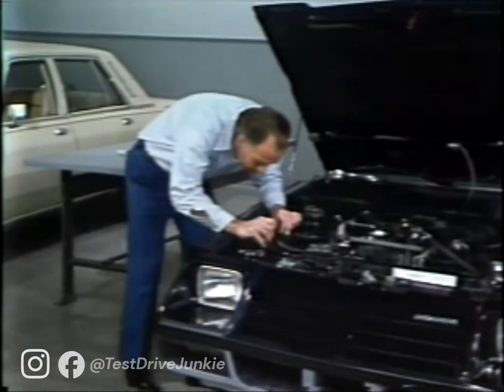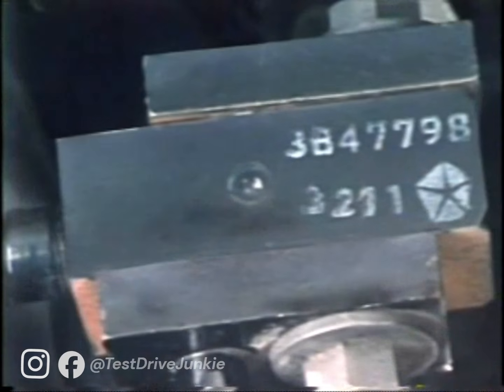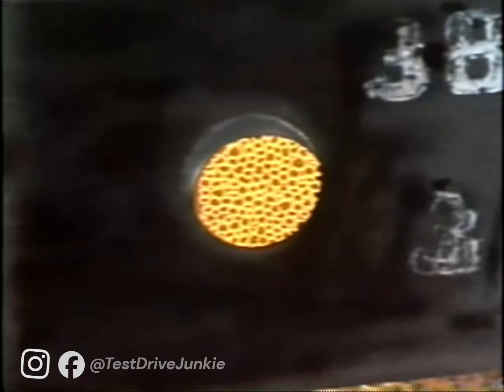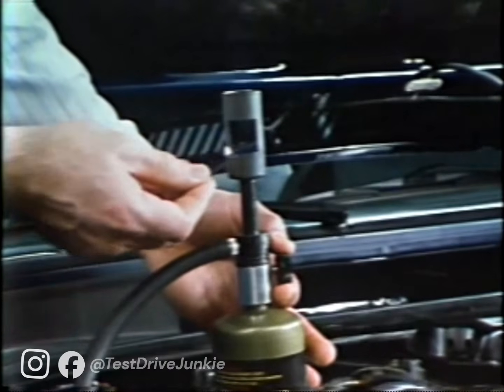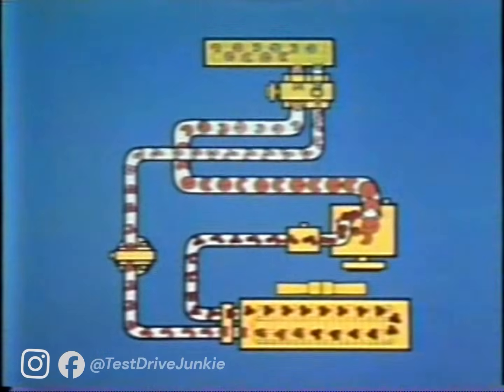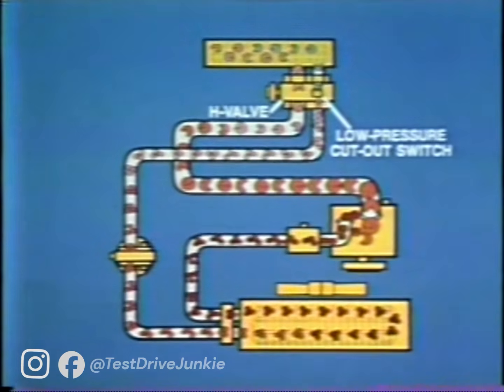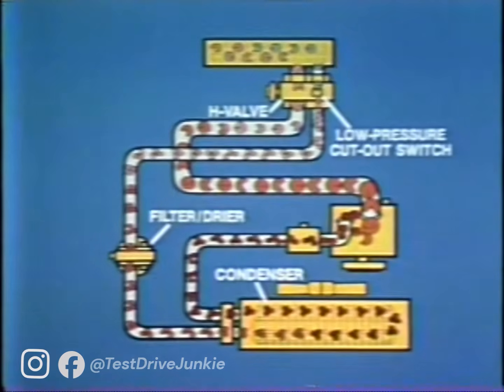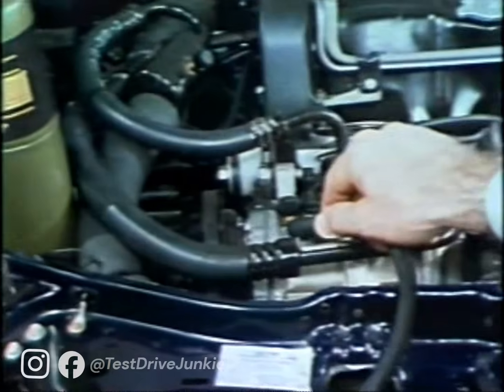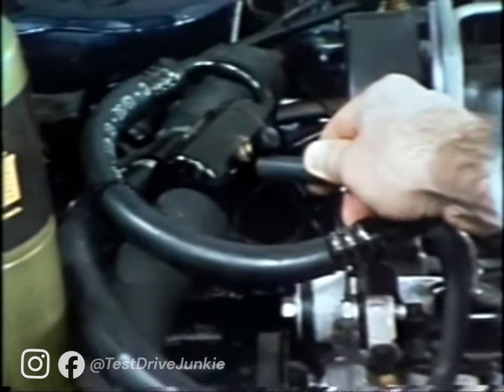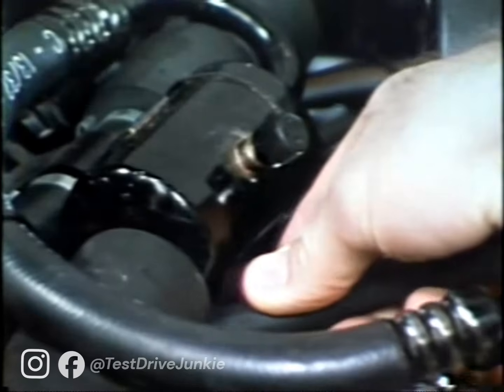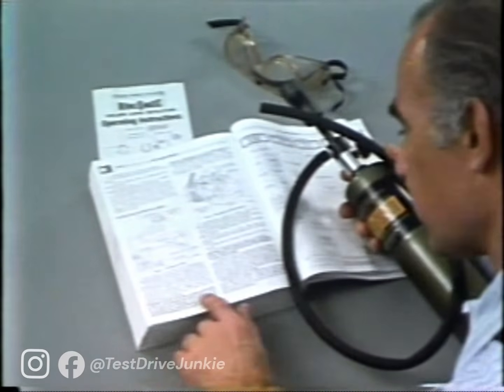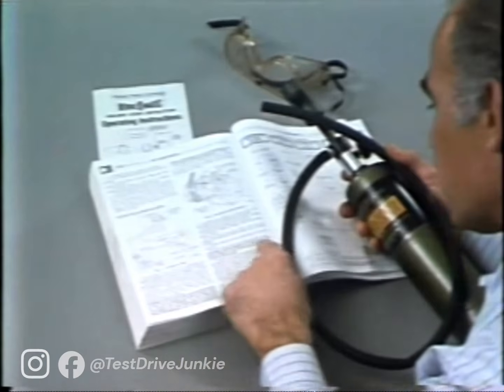Next, check the sight glass in the filter dryer to see if it is clear and free of foam. The presence of foam indicates a low refrigerant level, which could be caused by a leak in the system. Using a leak detector, check for leaks at all points, including the H valve, the low-pressure cutout switch, the filter dryer, the condenser, and the compressor. Remember that refrigerant is heavier than air, so you must hold the leak detector below the point being tested. Follow the procedures in the service manual and the instructions supplied with the leak detector.